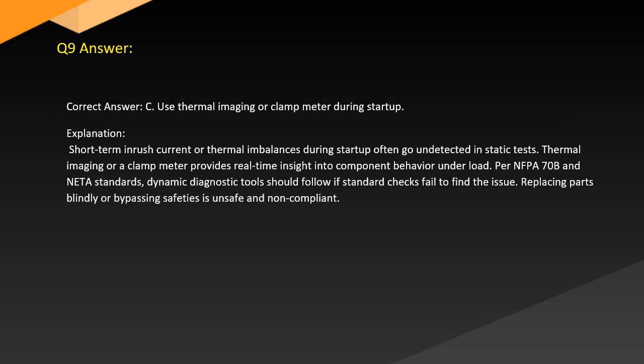Answer. Correct answer: C. Use thermal imaging or clamp meter during startup. Explanation. Short-term inrush current or thermal imbalances during startup often go undetected in static tests. Thermal imaging or a clamp meter provides real-time insight into component behavior under load. Per NFPA 70B and NETA standards, dynamic diagnostic tools should follow if standard checks fail to find the issue. Replacing parts blindly or bypassing safeties is unsafe and non-compliant.